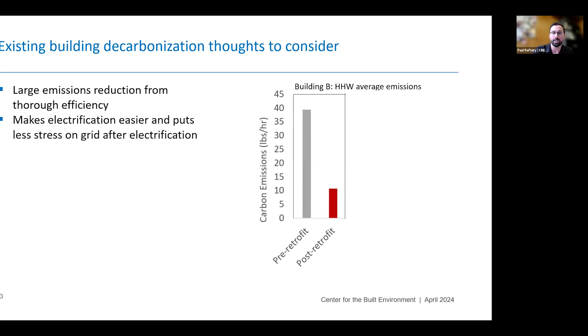We were able to reduce the emissions associated with the heating system, the site combustion emissions, by 70% in this building. And doing that first, before electrifying, will actually make electrification easier, because you're reducing hot water temperatures and reducing loads. It will put less stress on the grid after electrification.